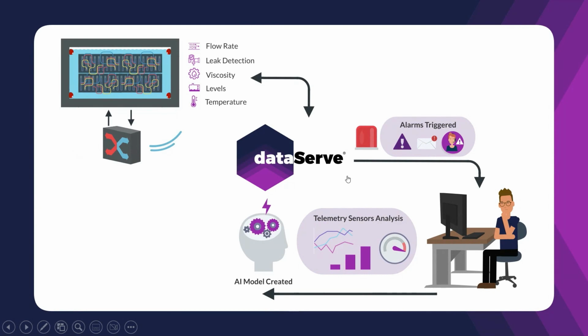It's also important to note that DataServe has an understanding of how components are linked together. Because if a temperature sensor within the coolant reports that we're now above the healthy range, it doesn't mean there's an issue with the coolant, and it doesn't mean there's an issue with the sensor. It actually means there's potentially an issue with some other thing that's correlated with it. So for example, maybe our pump has actually stopped working - the CDU, the cooling distribution unit, there's some sort of issue there, and that's why it's heating up.